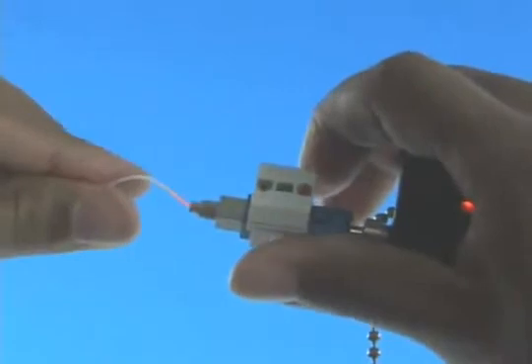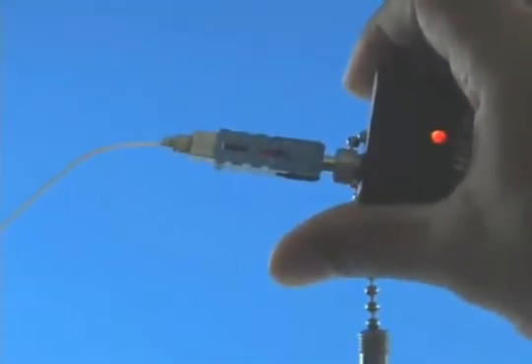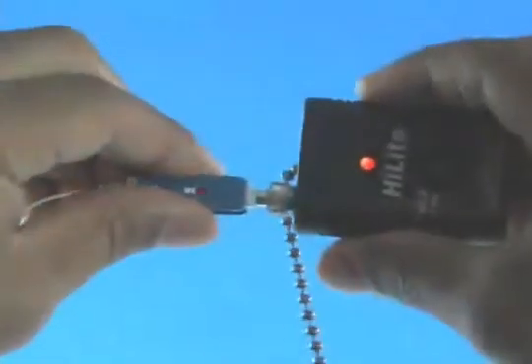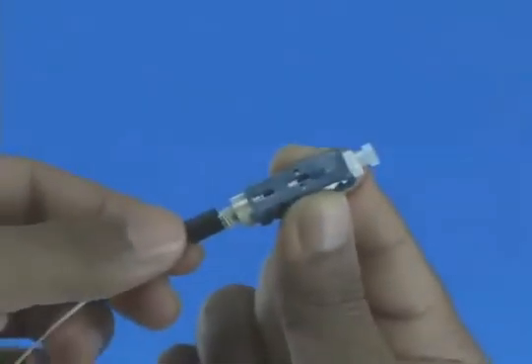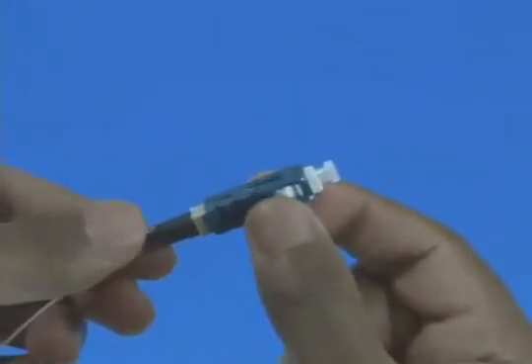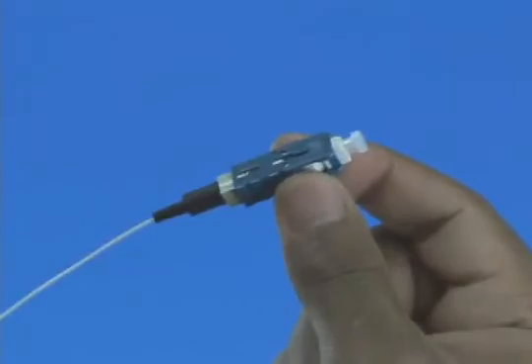Make a bend in the fiber to maintain connection. Squeeze both sides of the wedge clip to release the wedge. Discard the wedge clip. Remove the VFL from the connector. Place the dust cap back onto the connector. Slide the 900 micron boot onto the connector. Termination is now complete.